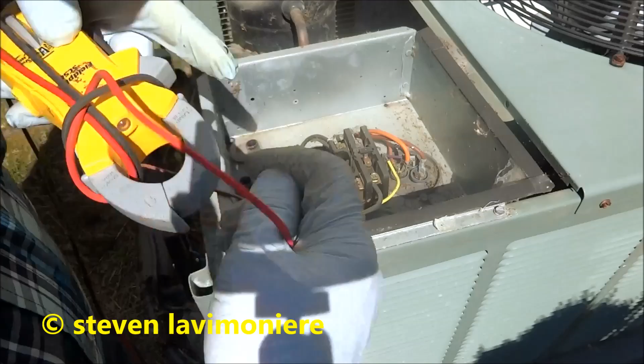Alright, I got the wire disconnected on the contactor. We're going to see what the ohm reading is across the low voltage. It's probably low. That's what fried the transformer. Yeah, 0.2. So yeah, 0.3. It's a bad contactor. So yeah, 0.2. No good. On the ohms, it should probably be around 14, 15 ohms. Anything around 19, 20 I change, or anything below 10 is coming out. So I gotta change the contactor.